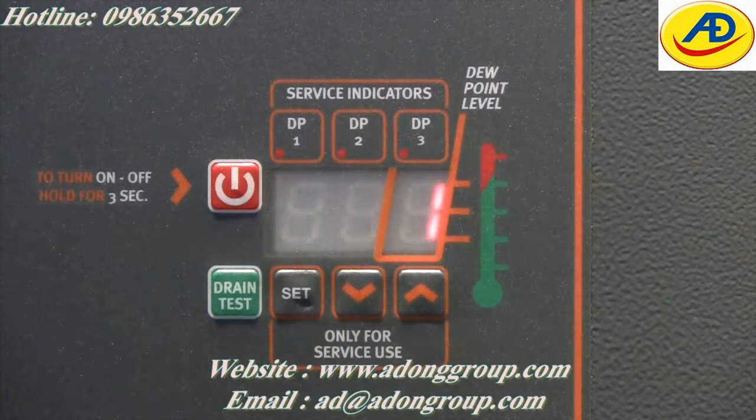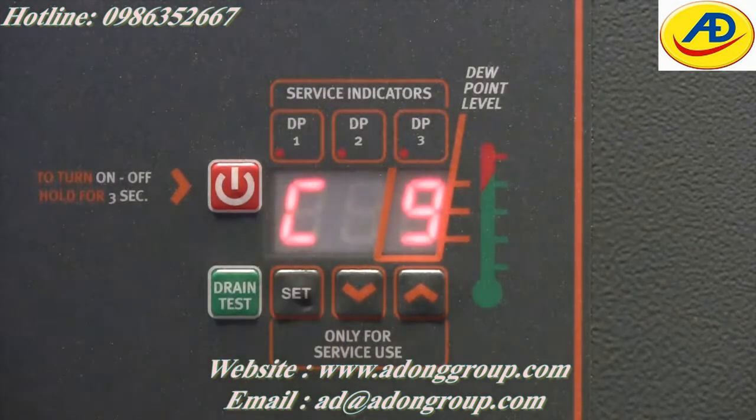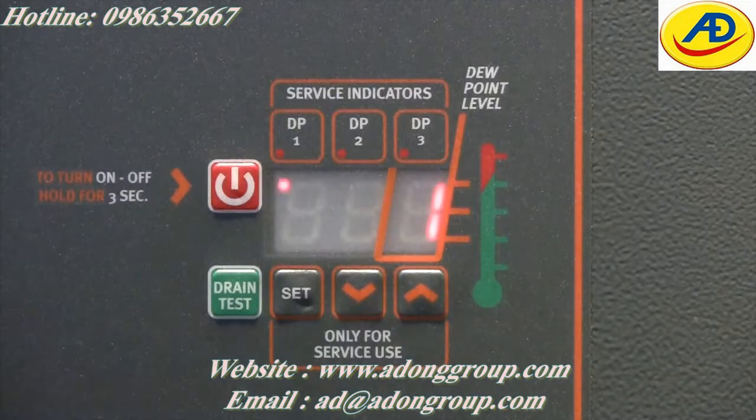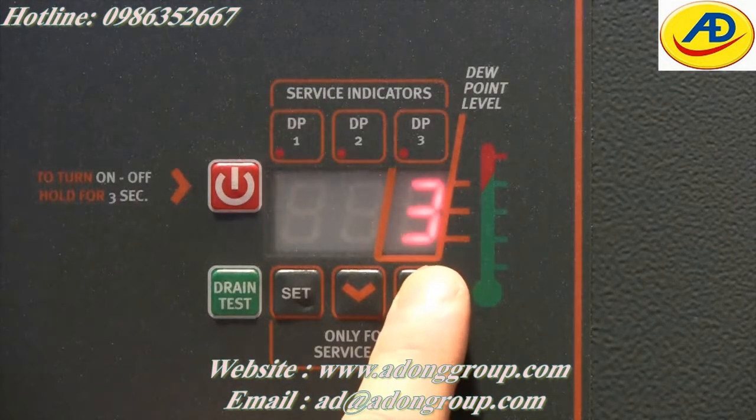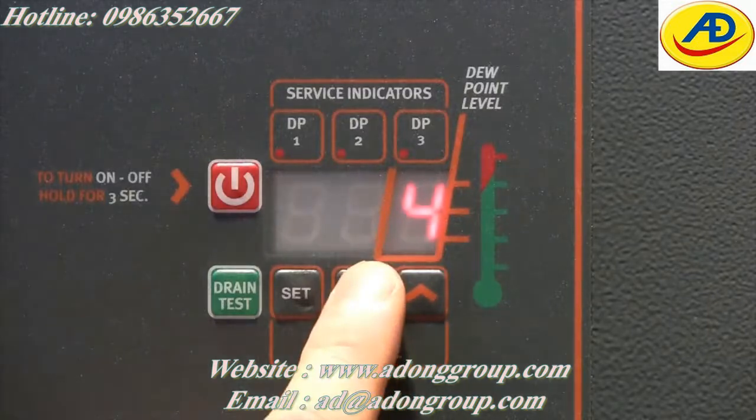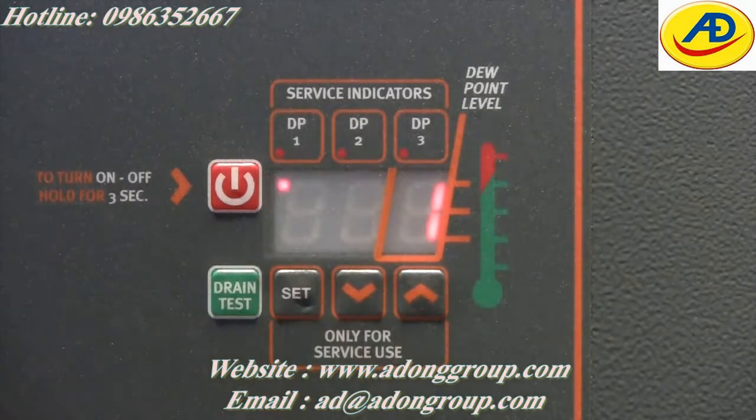To adjust a parameter, go through the above procedures until the corresponding value is on the readout. Press the up or down arrows to increase or decrease the value. The change must be made within 15 seconds. Once the value has been changed, press the set key for the value to be entered in the program. The set key must be depressed within 10 seconds of changing the value.